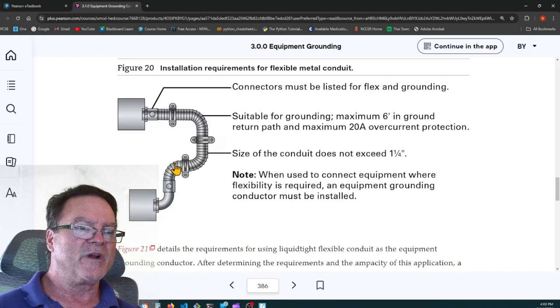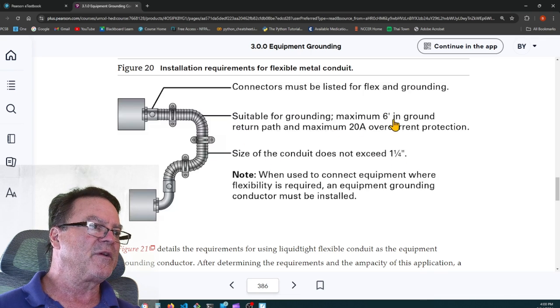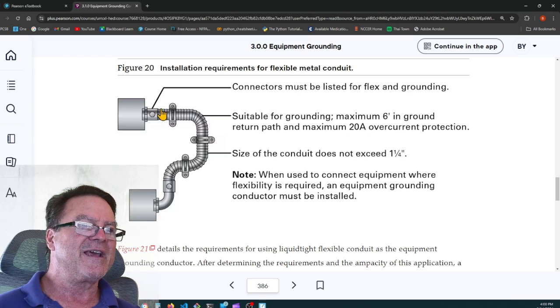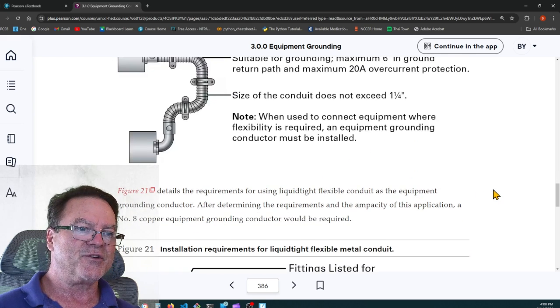So here's your flexible raceway, and the size of the conduit does not exceed 1.25 inches. It's suitable for grounding with a maximum of 6 feet in the ground return path and a maximum 20 amp overcurrent protection. The connectors must be listed for flex and grounding. When used to connect equipment where flexibility is required, an equipment grounding conductor must be installed internally.